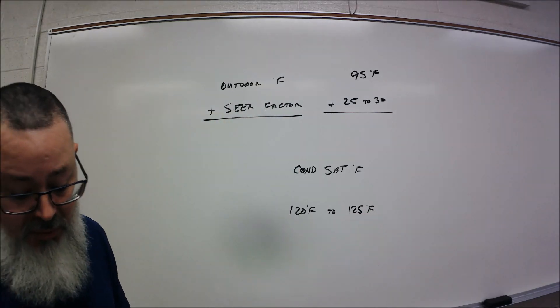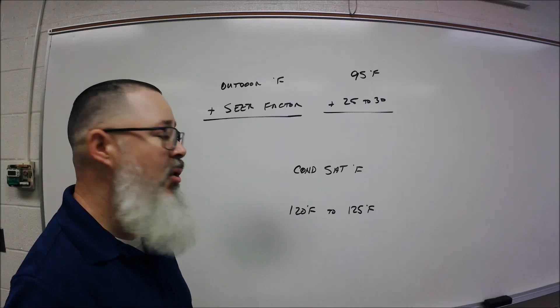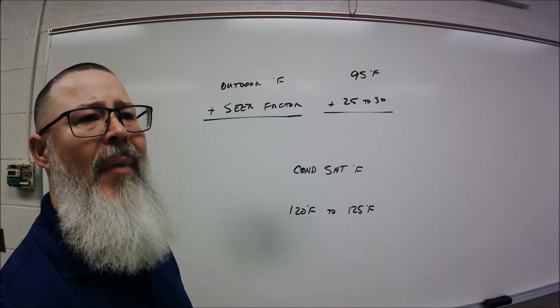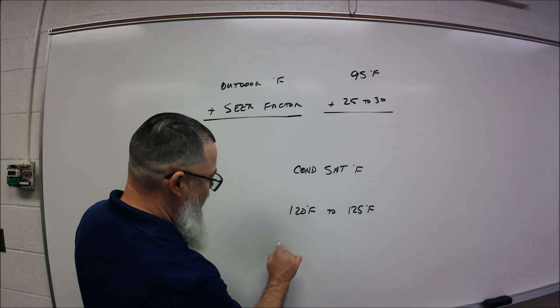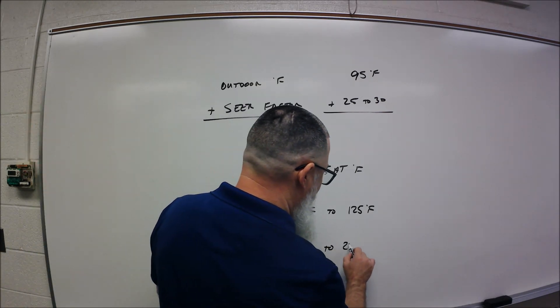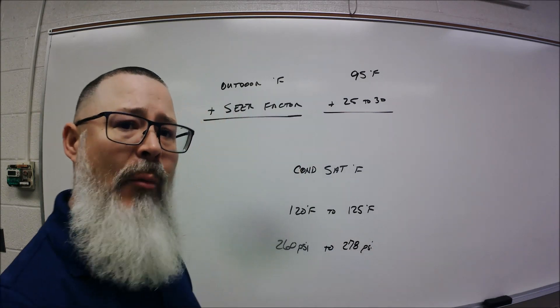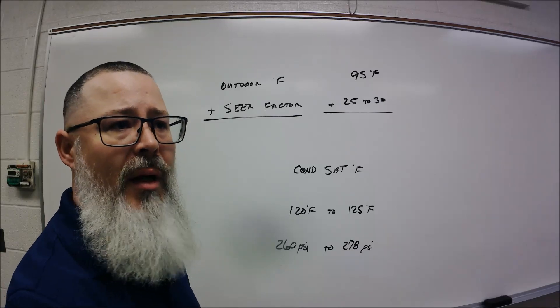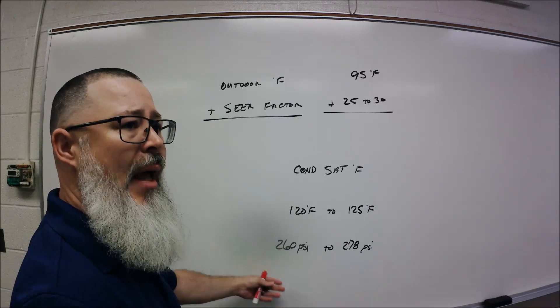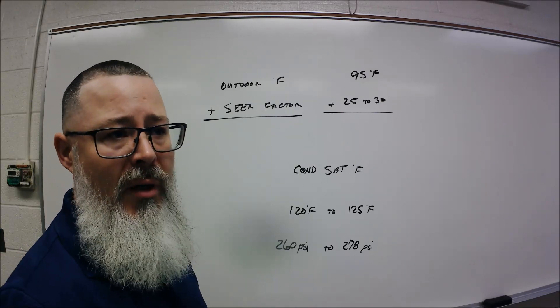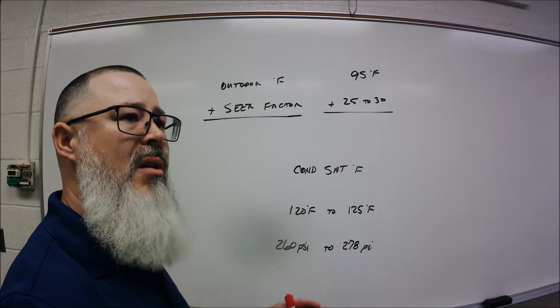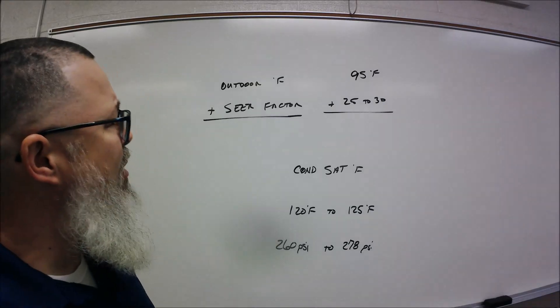Now if you have an R22 system, you can look up 120 degrees on your pressure-temperature chart — that's somewhere between 260 and 278 PSI, which would be the appropriate saturation point and pressure. I try to work mainly in temperatures first. If this was an R410A unit, you're not going to have 260 PSI at a 120-degree saturation point — you're going to have somewhere around 415 PSI. So you can adjust the pressures depending on your refrigerant.